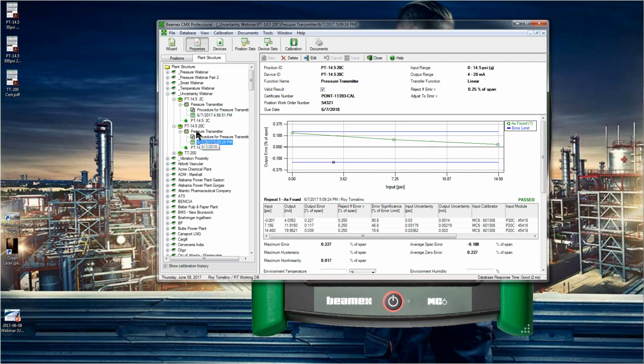If I go back to the 300 PSI module and we look at the data, let's look at the table down below, our first test point, our input uncertainty was 0.03 PSI. So this is the uncertainty from the perspective of the calibration standard, which is the pressure module inside the calibrator. Now, 0.03 PSI, remember that number. If I go up to the 30 PSI module, the input uncertainty is different. It has one more decimal place. 0.003 is our uncertainty from the calibration standard.